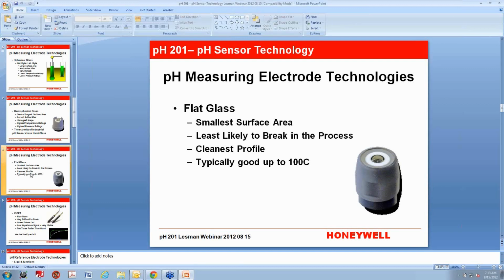And the reason for that is, again, that weld line where the actual pH-sensitive glass is welded to the stem. That weld angle is 90 degrees, and that is going to be the weakest of the weld angles. So at a high temperature, when the fluid behind that glass starts to volatilize, when you get over the boiling point, that can actually cause it to break right along that weld line. And this is pretty typical for what I would consider good quality pH-sensitive glass. That kind of runs across the board for most manufacturers.